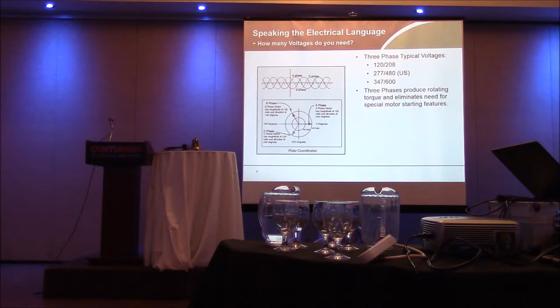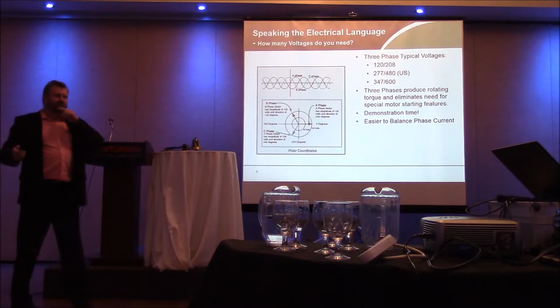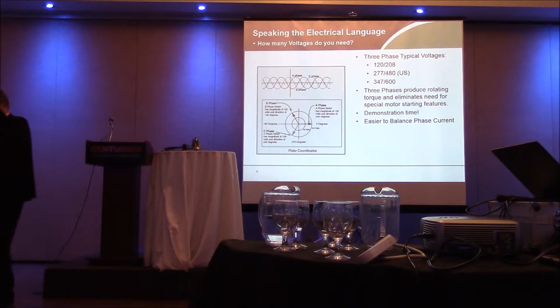3-phase power for a motor like that makes it easier for me to balance the current, which means I don't have underutilized equipment. I don't have equipment with 1 phase that isn't carrying enough load, which means I can put in smaller equipment, which means I can make my electrical room smaller, which means you can make your mechanical room bigger. It also means I'm bleeding less energy off into my electrical room, which means you don't have to get rid of as much heat. We'll talk about that more in a minute.